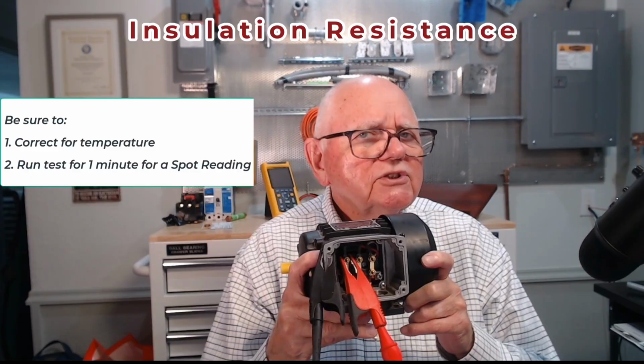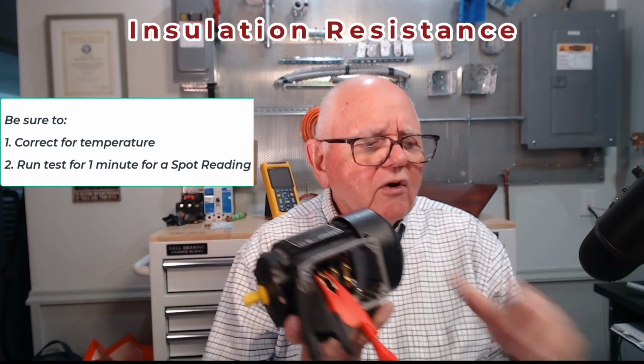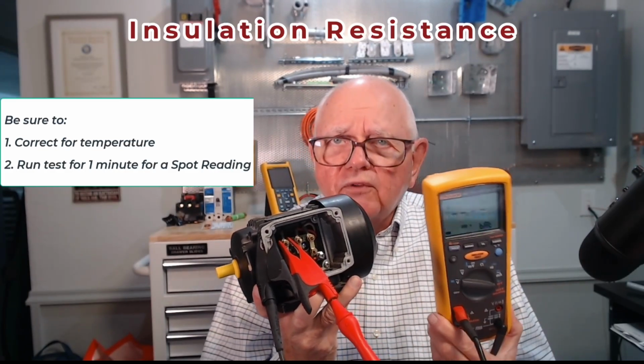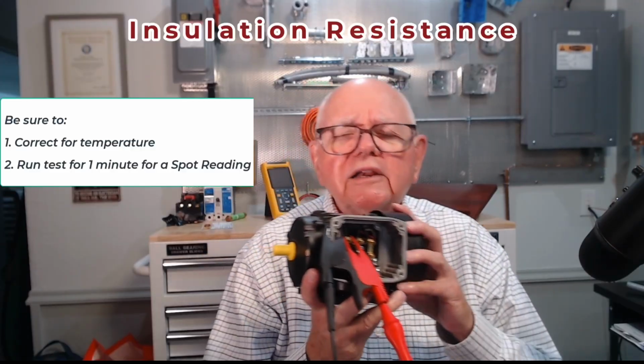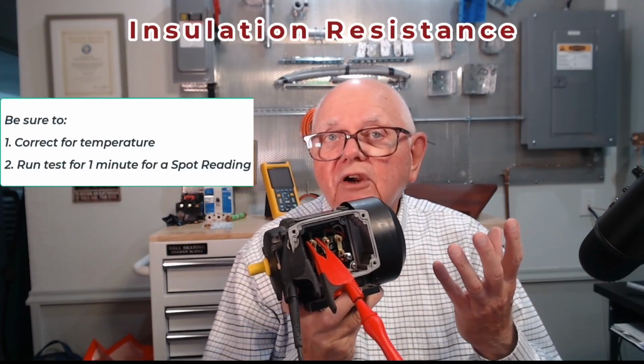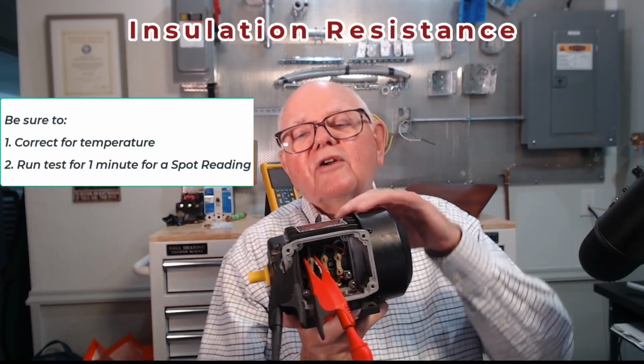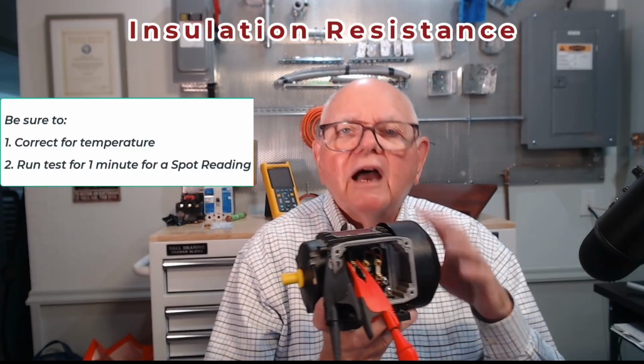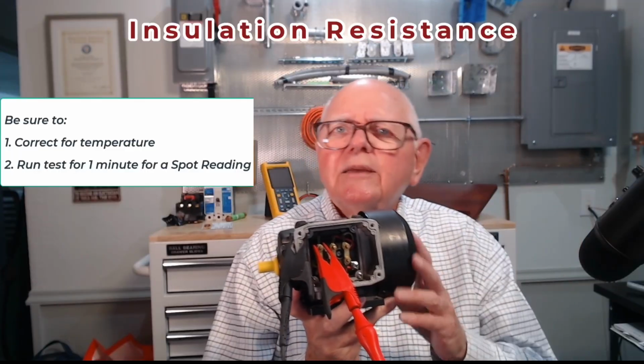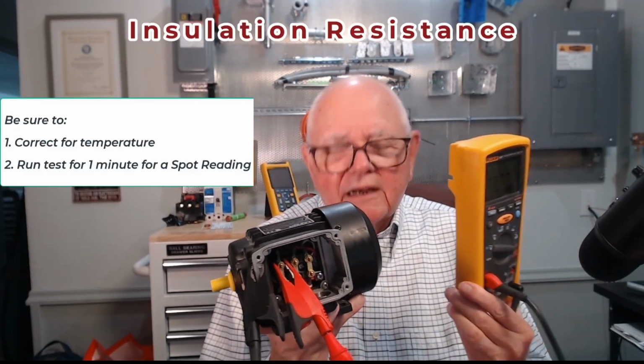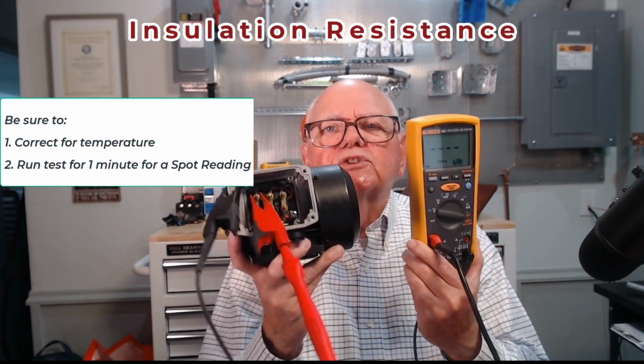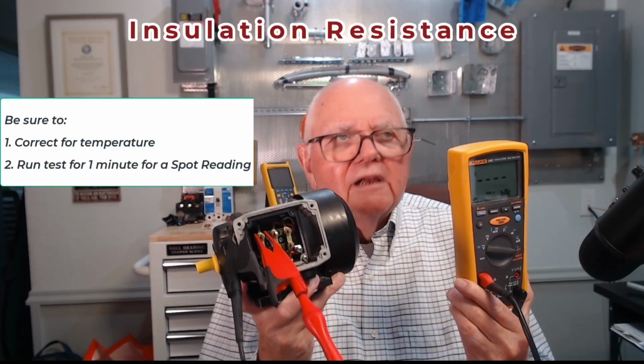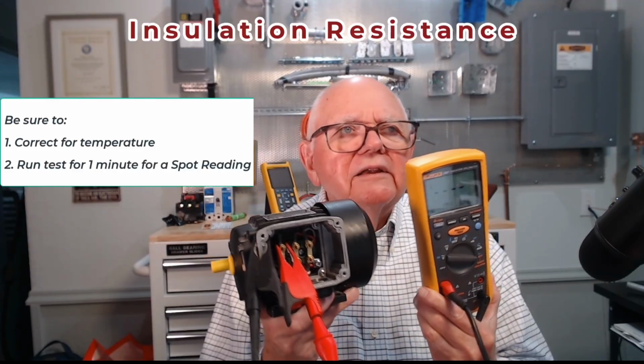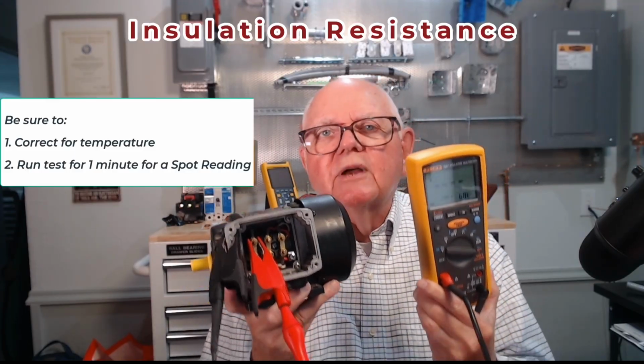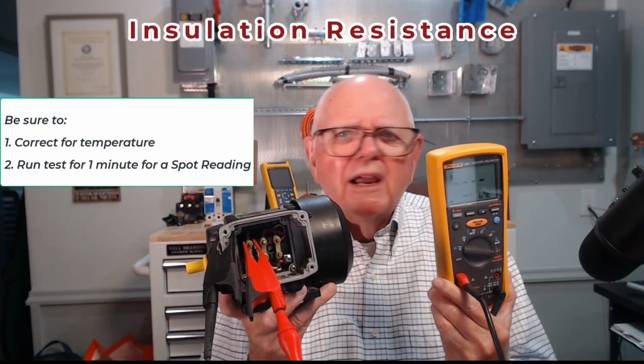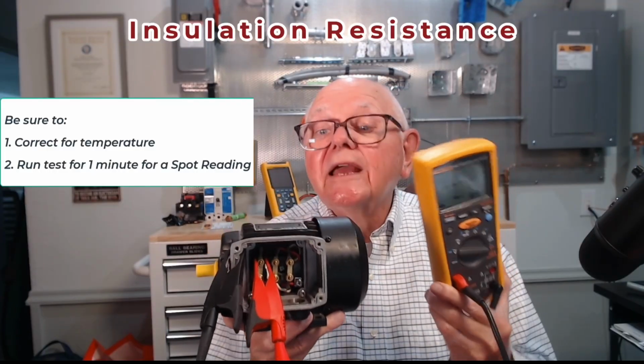The other big issue that I've run into with my insulation resistance testing is how long I am going to apply that insulation test voltage. When I apply my test voltage to my insulation and my windings, there are three currents that flow. There's dielectric absorption current, there's capacitive charging current, and then there's the actual current that leaks out into the windings. It's going to take a little bit of time for my dielectric absorption current and my capacitive charging current to stabilize out. So, once again, if I come along today and take an insulation resistance reading and I let my tester run for 13 seconds and then I get a certain reading, next month somebody else comes along and does the same maintenance test and they let their tester run for 2.5 minutes while they go and do something else and then come back. Our readings may not be comparable then, right? The only real reading we're concerned about is the leakage current.